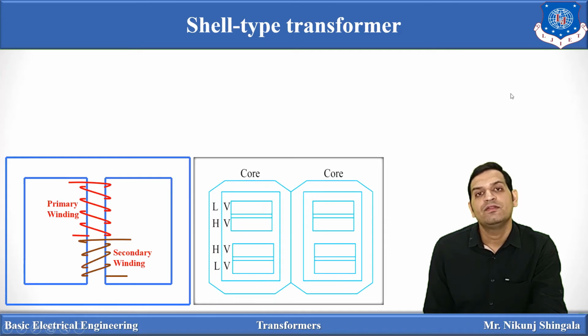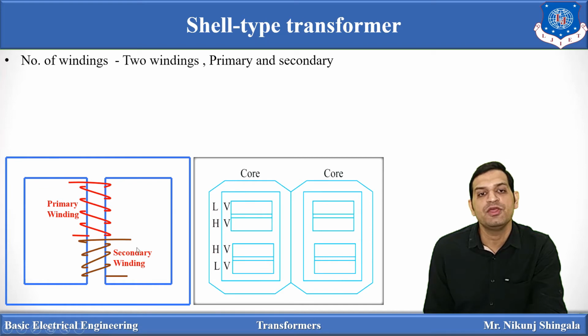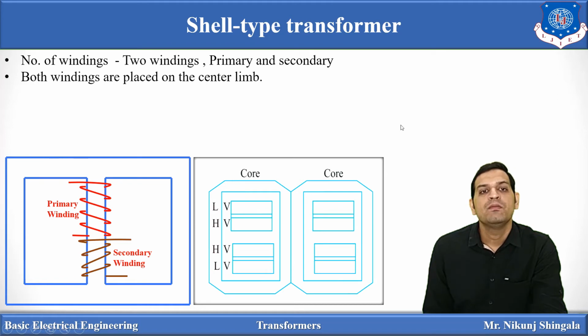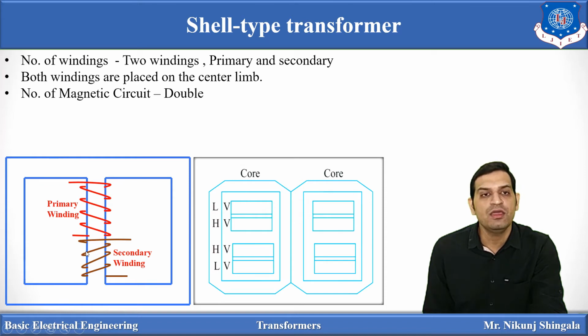Now moving towards the next one, which is the shell type transformer. As I told you, in the shell type transformer, both windings are on the central limb. It consists of three limbs, as you can see here, and two yokes. It consists of two magnetic circuits, whereas in the core type transformer, only one magnetic circuit is there. The number of windings is two, primary and secondary. Both windings are placed on the central limb, and if both windings are placed over here, we can say the winding is surrounded by the core. Some part of the winding is surrounded by the core.